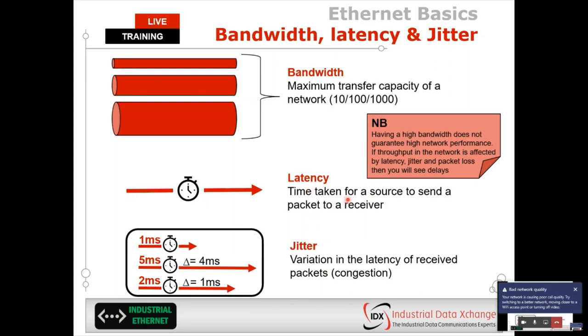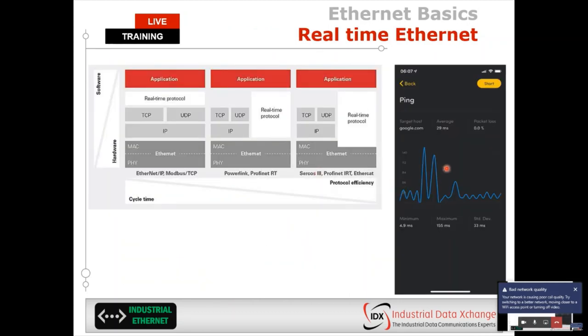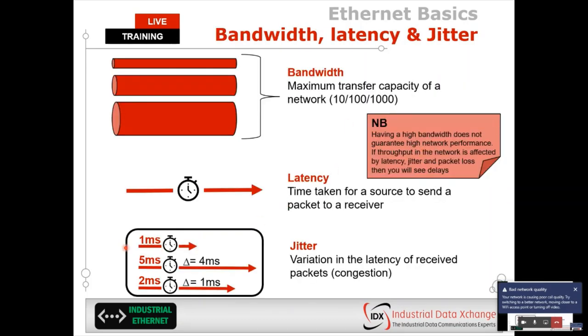So those are things that affect your latency. Jitter, then, is a variance of latency. As we saw with our previous telegram, our standard deviation from ping times showed quite a huge amount of jitter, or change. For example, my first telegram went out at 1 millisecond, my second at 5 milliseconds — a difference of 4 milliseconds, so my jitter is 4 milliseconds. My third went out at 2 milliseconds, so my jitter there is 1 millisecond. There will always be a little bit of jitter on any industrial Ethernet network, but it's about managing that jitter to ensure it doesn't affect your communications on the network. There's a certain threshold we'll discuss a little later.